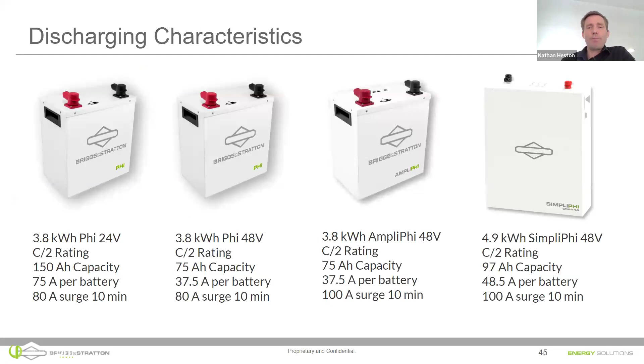The ratings are here. I'm going to send this slide deck. I want to jump into some newer slides. But I do want to point something out on the battery state of charge and voltage, because this is something that often gets confused. You'll see a voltage on your inverter that says 55 volts. Well, the batteries, when they're at 100% state of charge and just resting, are going to be at a voltage of around 53.5 volts, depending on the temperature slightly. So why would you be seeing a higher voltage on your inverter or your charge controller? Well, you must be in a charge cycle.